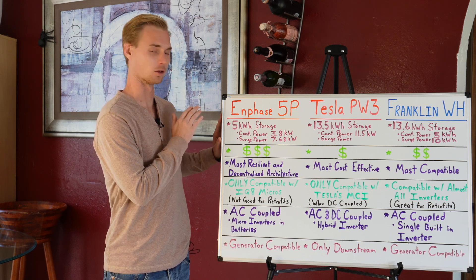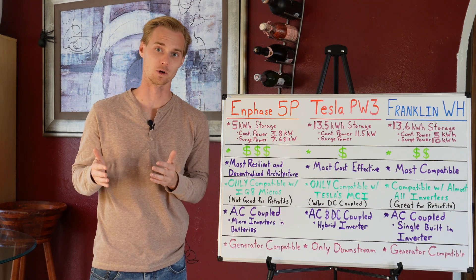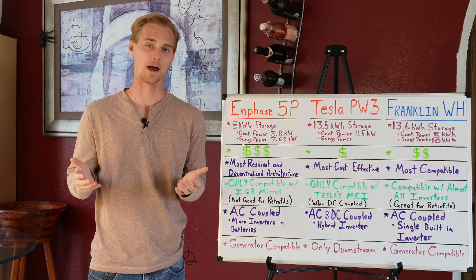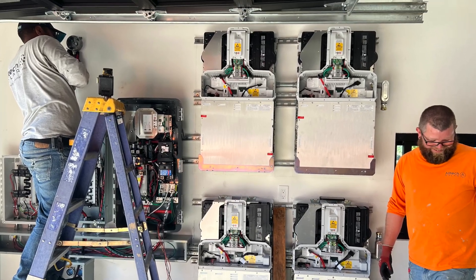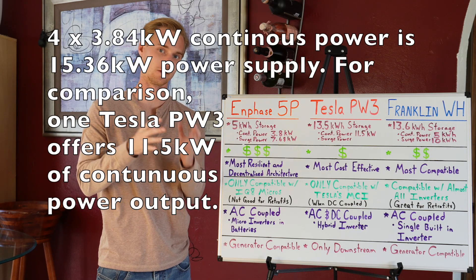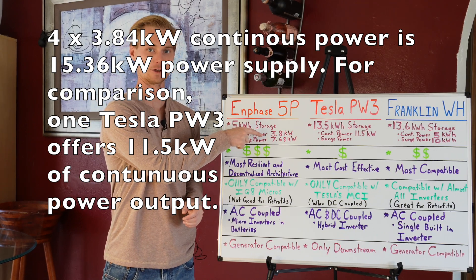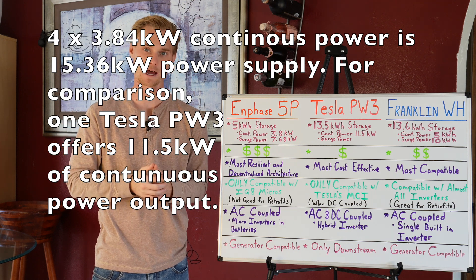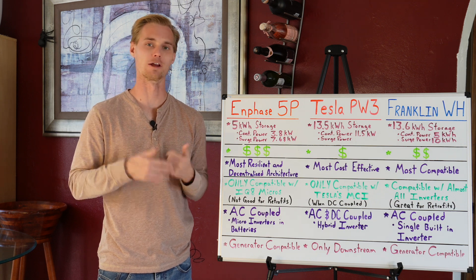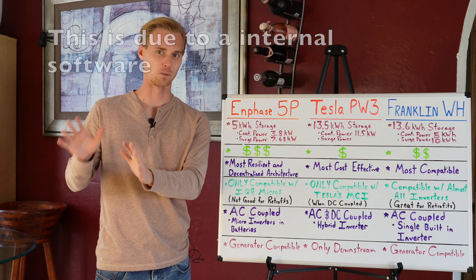When you look at the Enphase 5P battery, it's only a five kilowatt hour unit. It's not made to be a 13 or 10 kilowatt hour battery. You actually stack multiple 5P batteries next to each other, and then you get the benefits of all the inverters because the inverters are built into each battery. You basically multiply these figures by two, three, or four depending on how many batteries you have. When you get to a certain point there could be some limitations around 40, 50, or 60 amps of potential backfeed, but that's a little more advanced for this video.